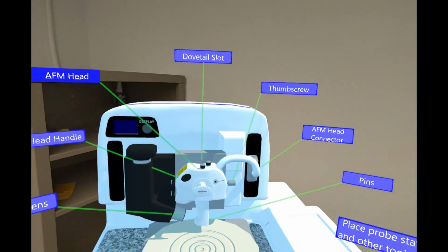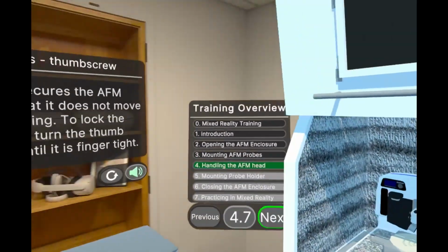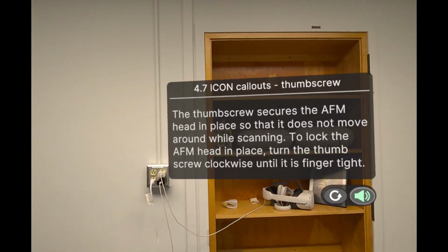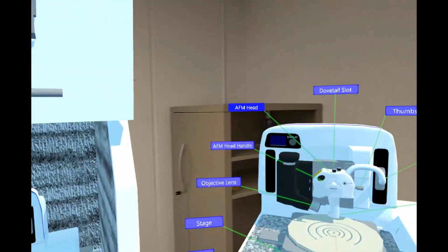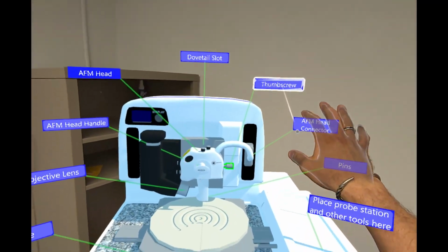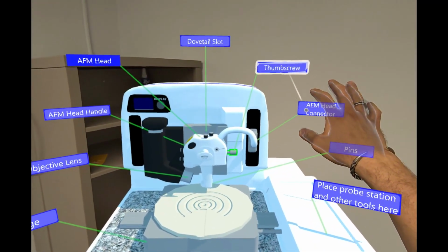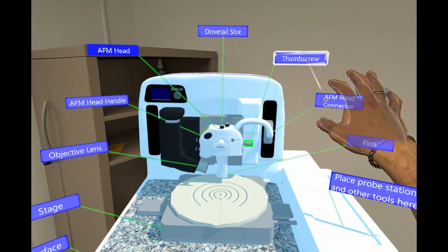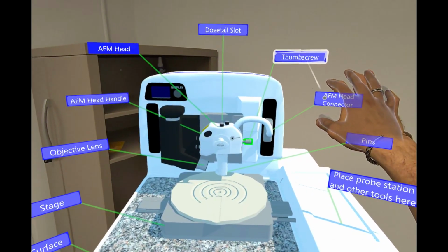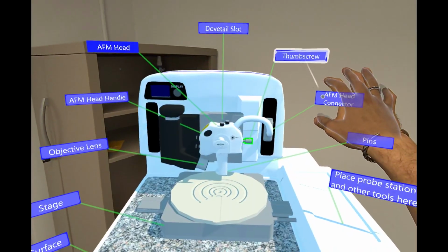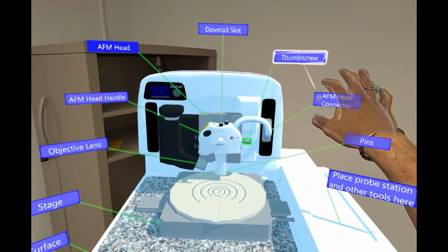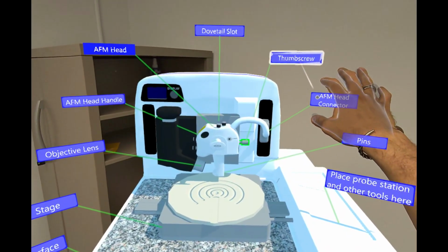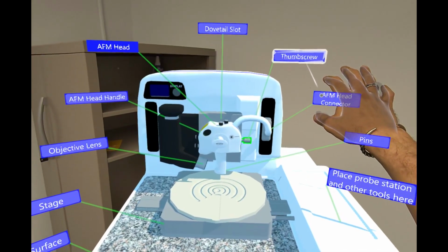The thumb screw secures the AFM head in place so that it does not move around while scanning. To lock the AFM head in place, turn the thumb screw clockwise until it is finger tight. Turn the thumb screw counterclockwise several turns to release the AFM head to be able to lift it. Continuing to turn the thumb screw past several turns should be avoided as you risk removing the thumb screw completely.